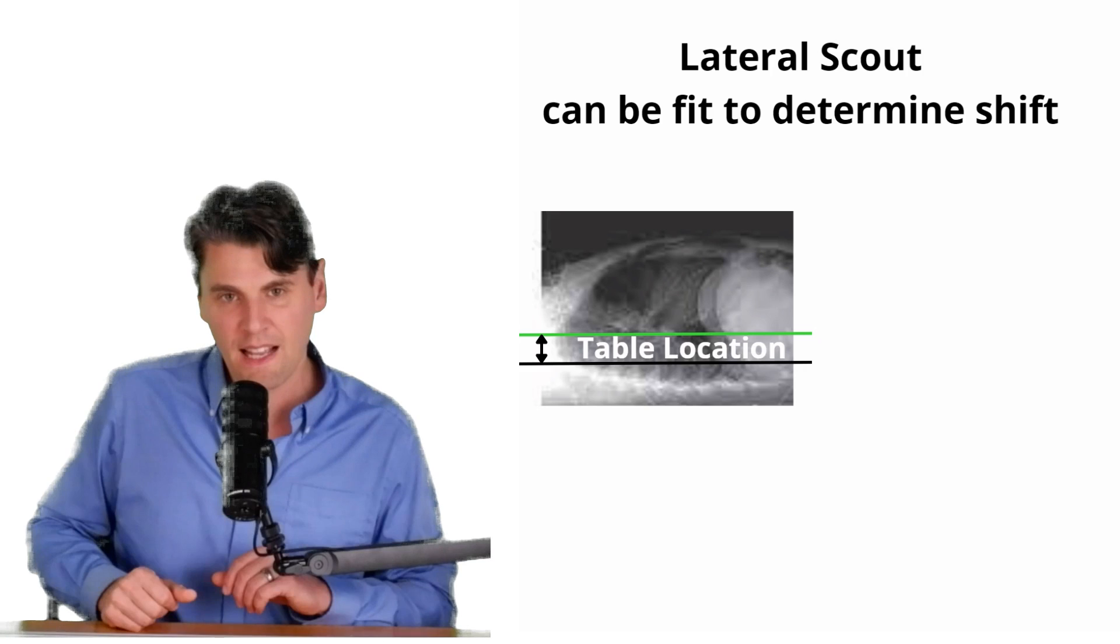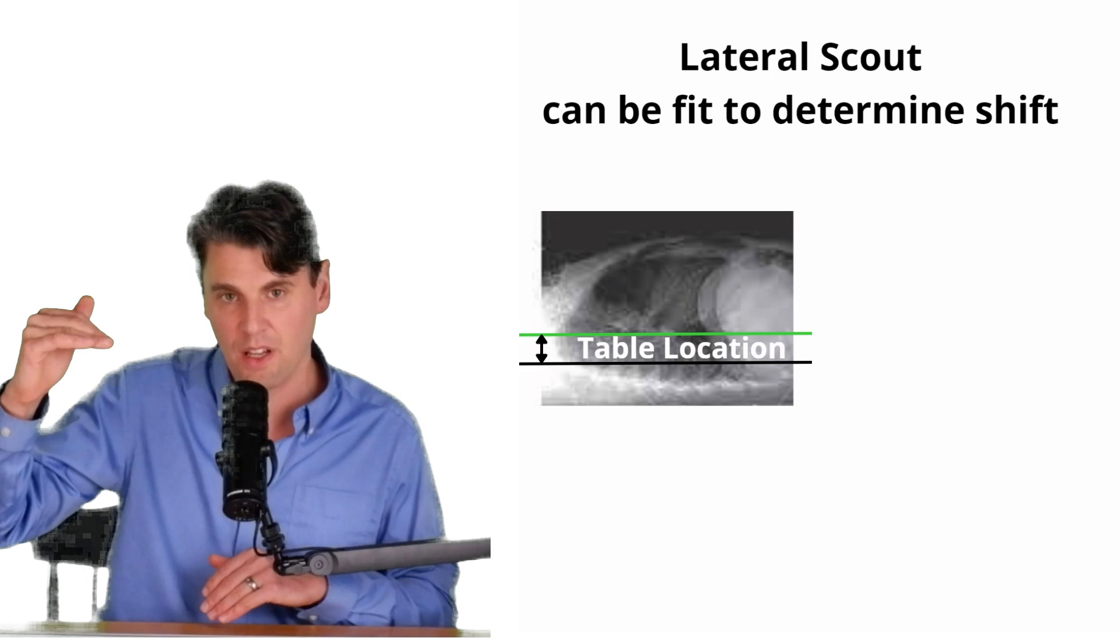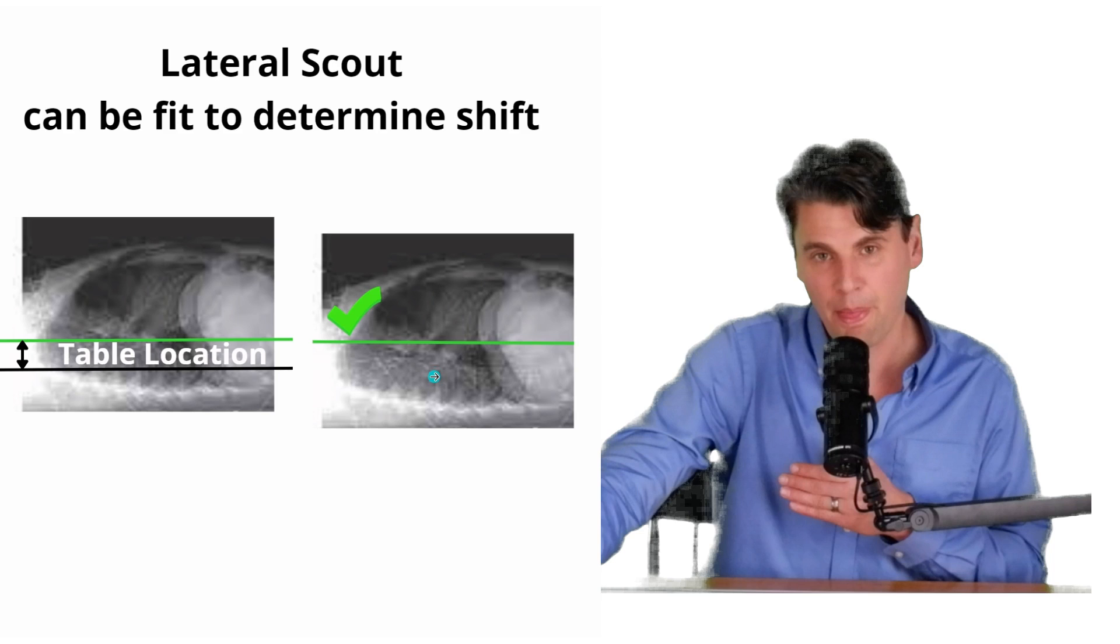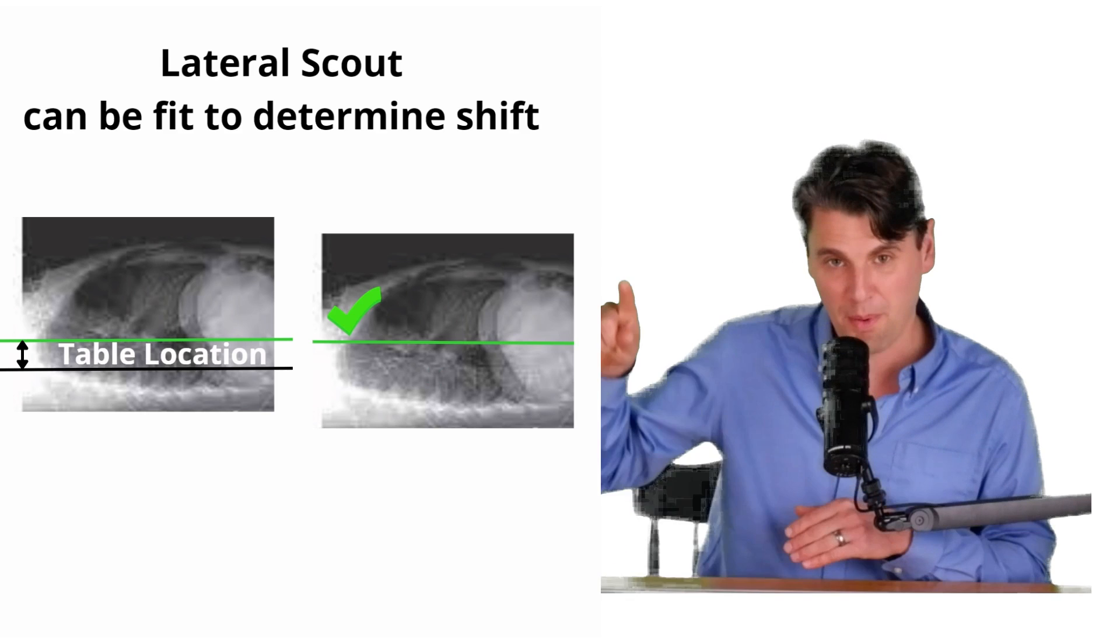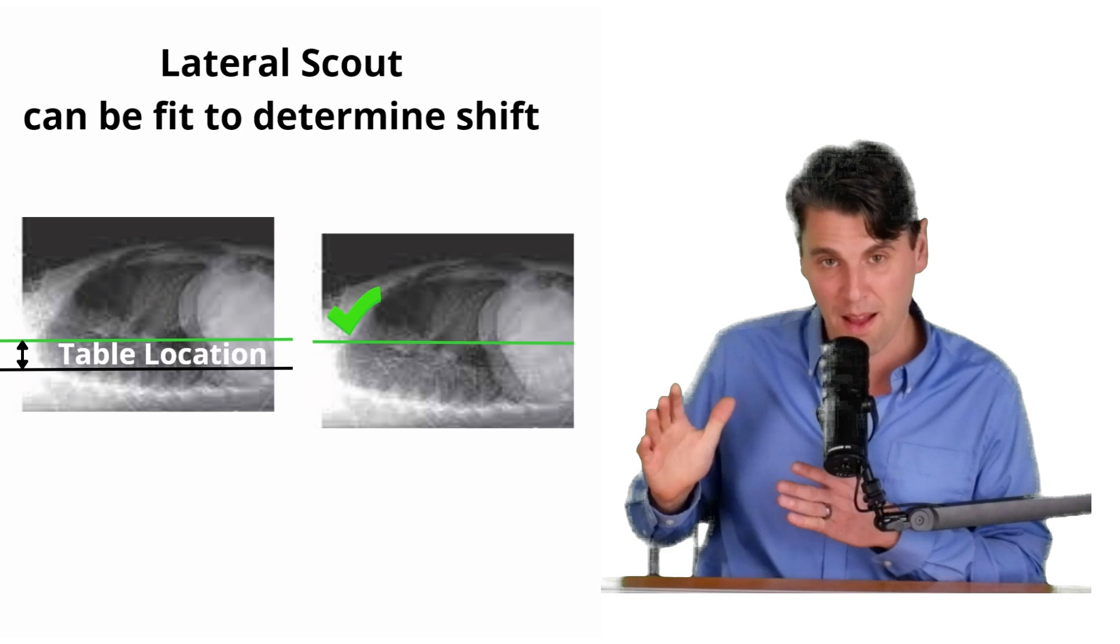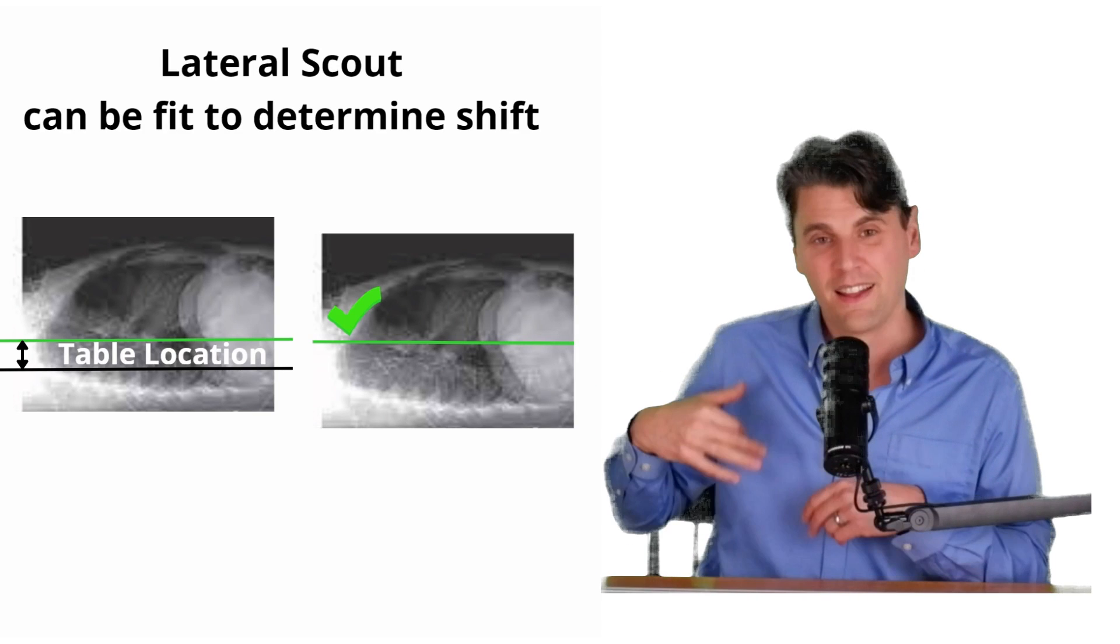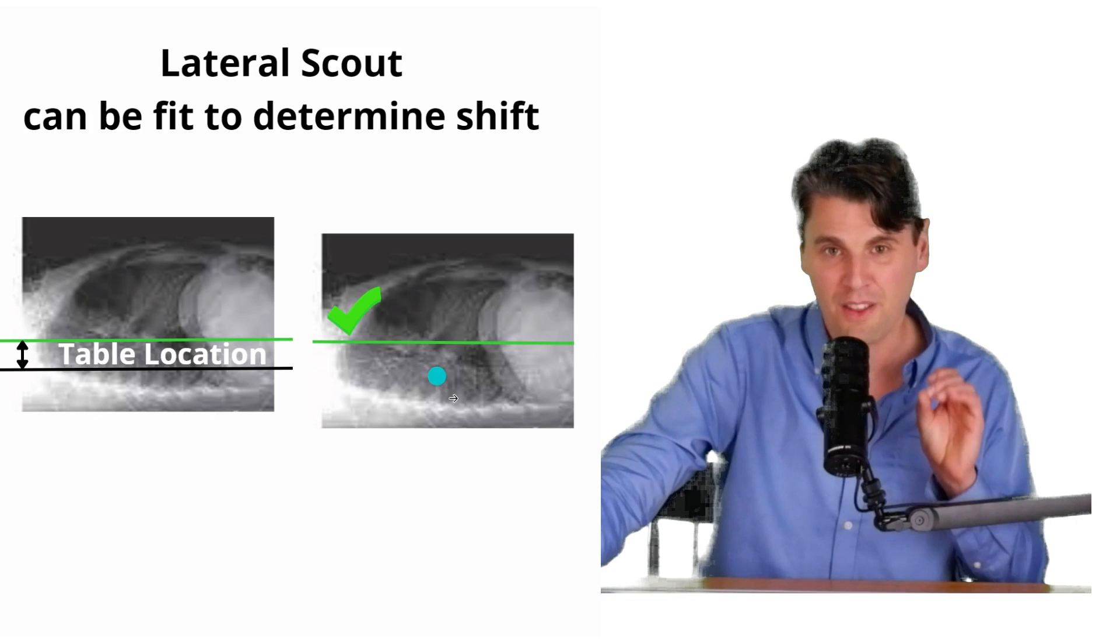Depending on how the vendor has it implemented, it could say something like go to this given table position, and you would go into the system and put that given table position. So if you have the patient relatively well positioned right away, you can get the green checkmark that says good job. Or if you do the update and get the patient well positioned, you'll get the green checkmark that says good job, you have the patient well positioned in that up down direction, you're ready to go with good patient centering.